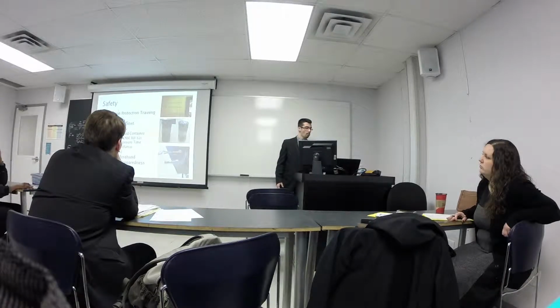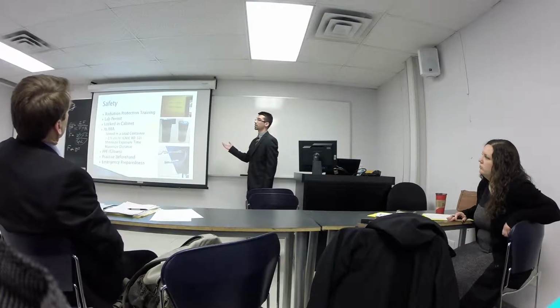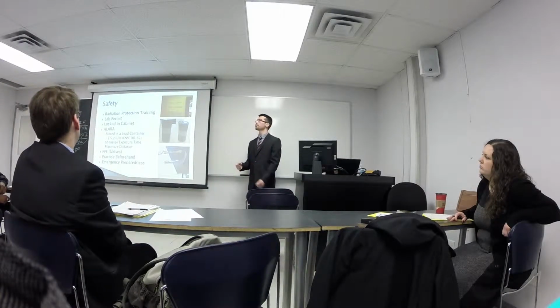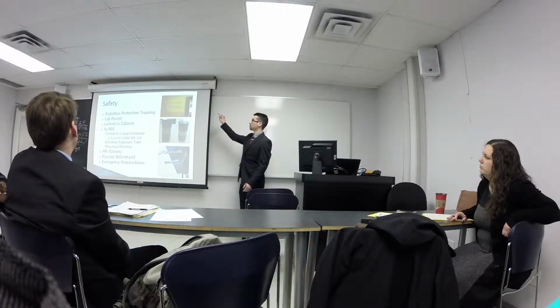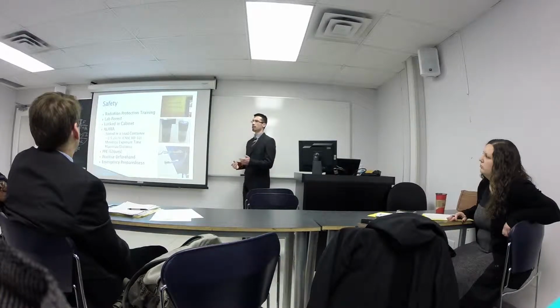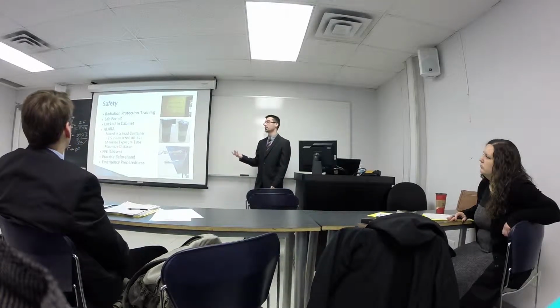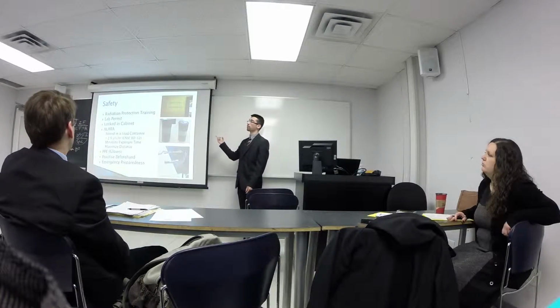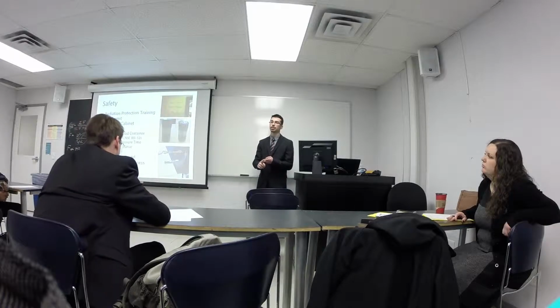In terms of safety, all three of us underwent radiation protection training here at the university. We had a permit for the lab so that we could store the sources there, so we had to mark the lab as a radiation zone. The sources were always stored in a locked cabinet, which only I have a key to, and the RSO at the school. They're stored in this lead tank, and this was basically done for ALARA. It was actually a requirement to bring the dose rate down to 2.5 microsievert per hour. If you are storing sources in a lab or a medical setting, this is what we have to abide by.